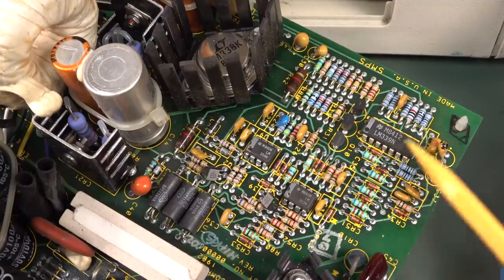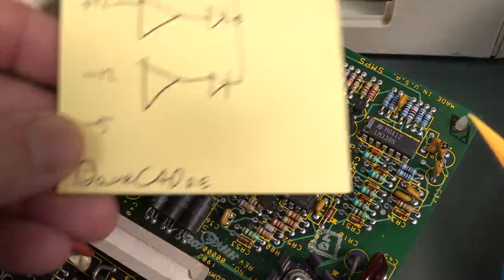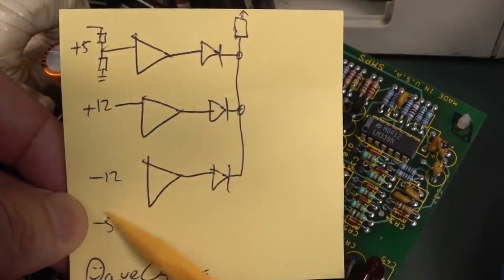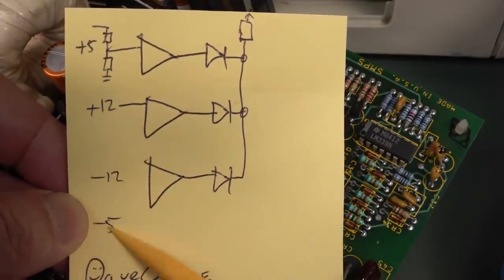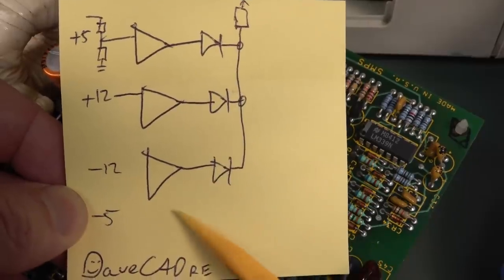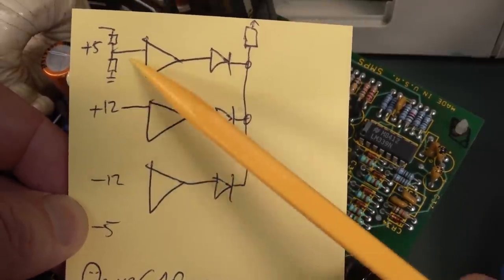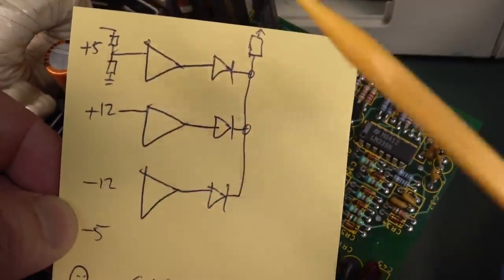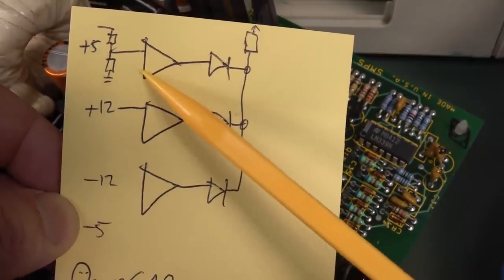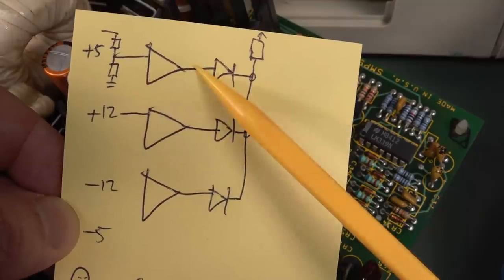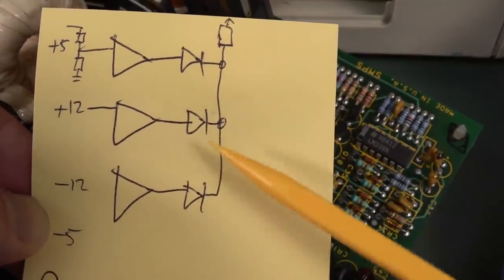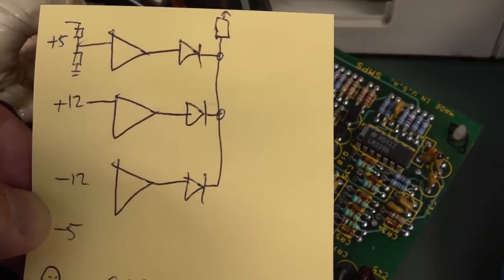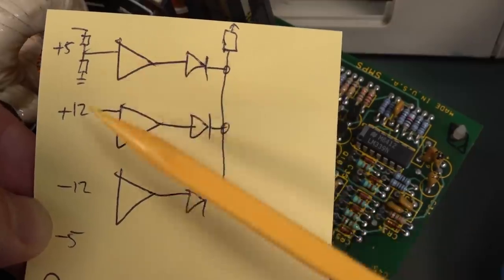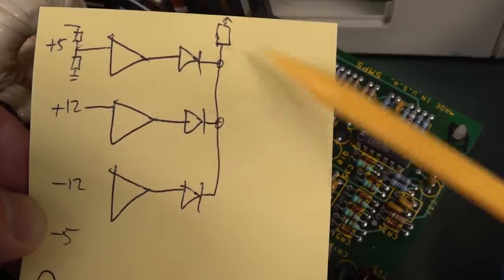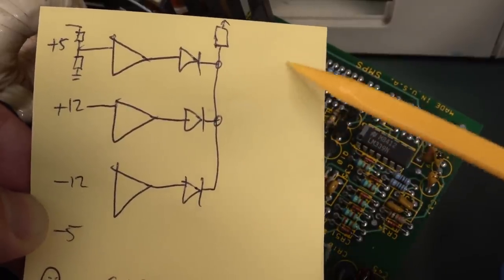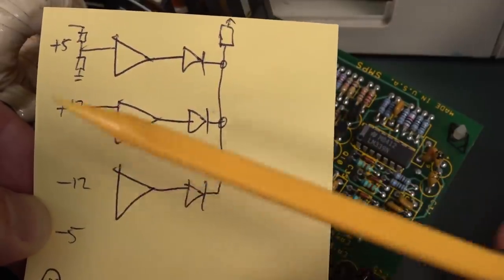And with this power good here, with this LM339 quad comparator, what's going on here is a rough sketch. We've got all the power supplies coming in. There might be more than this. It'll be plus 5, plus 12, minus 12, minus 5. Should have drawn an extra one there. But they all basically go into comparators here. There'll be a voltage reference on these pins. So it's basically, are they above a certain spec? So for 5 volts, you might put 4.75. Is it above that? Your typical 5%. Then it gives, okay, I'm good. And how they're doing this diode arrangement here, you could do it as an AND array or an OR array. It depends how you configure the positive and negative inputs here and how you compare them. But basically the idea is that this will give an output happy if all of the inputs here are above their thresholds.